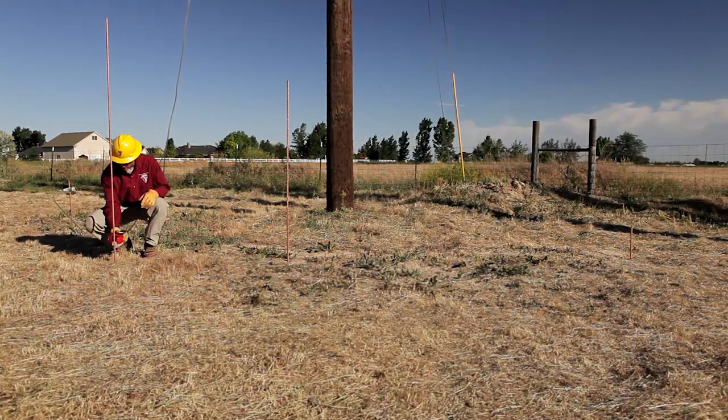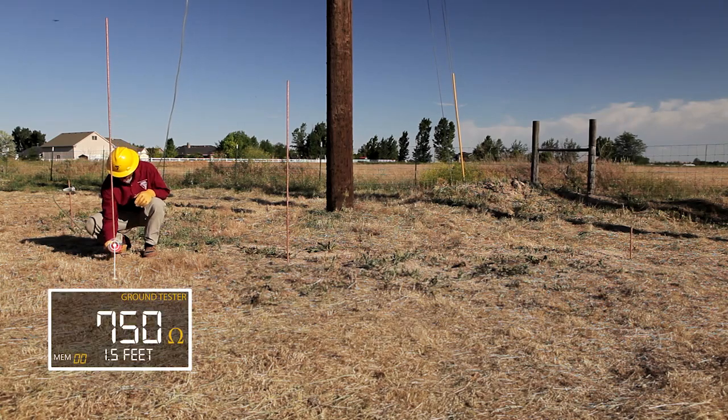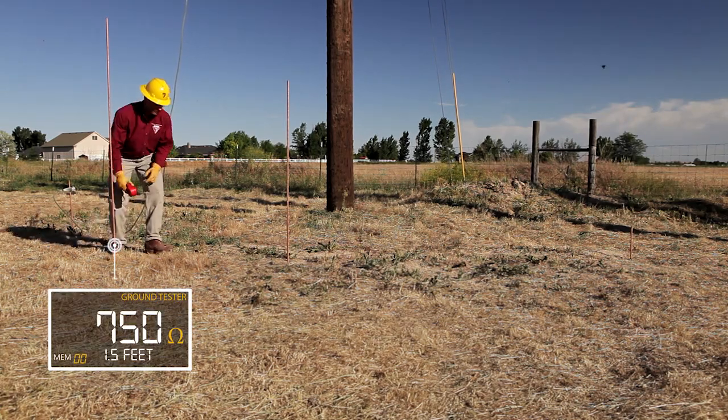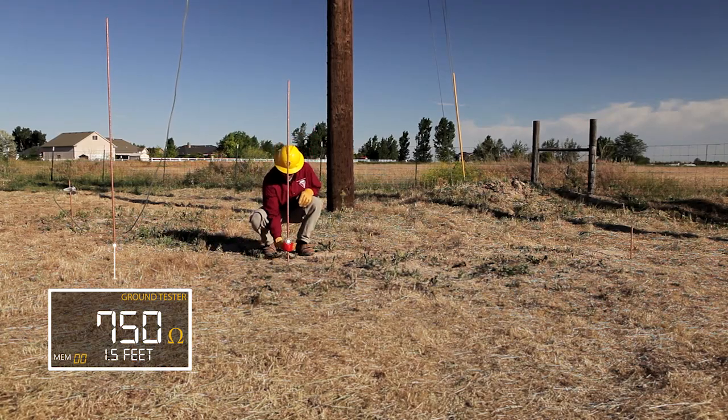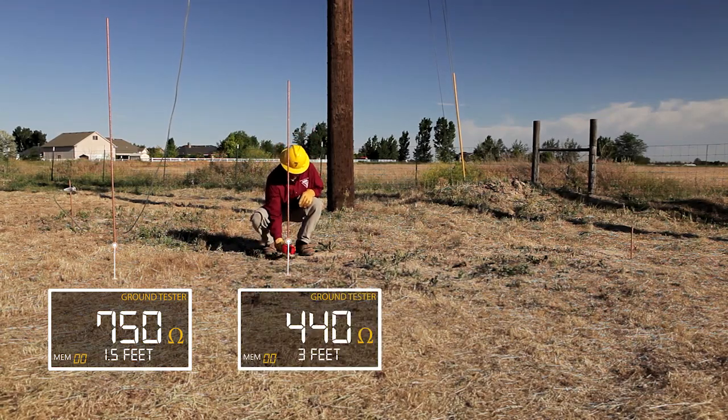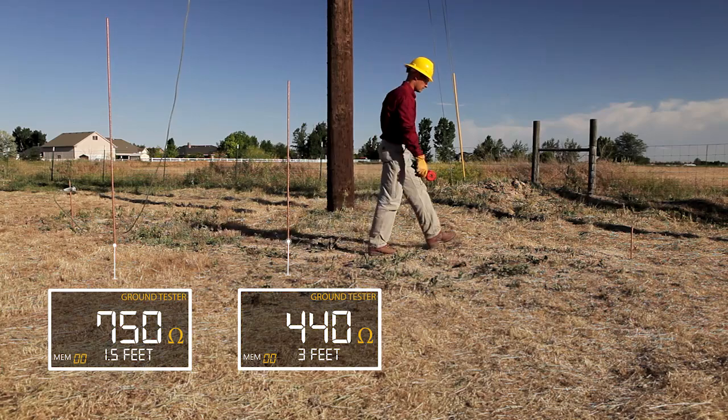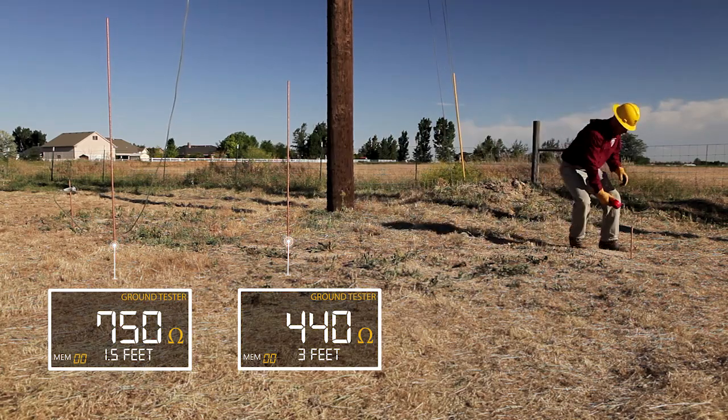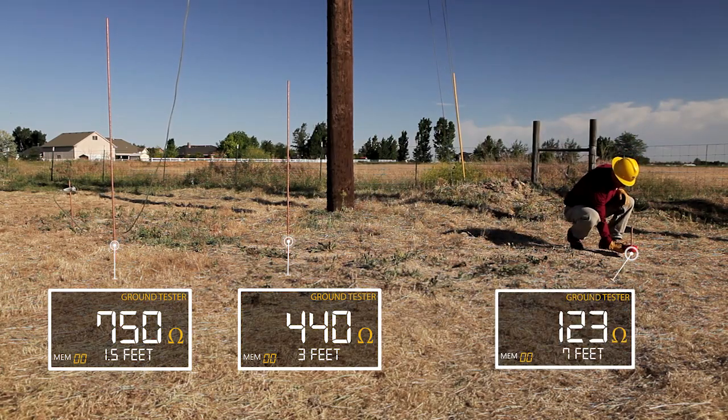Our first ground rod is only driven one and a half feet deep and has a ground resistance of 750 ohms. Our second ground rod is three feet deep and has a ground resistance of 440 ohms. And our last ground rod was driven seven feet deep and is reading 123 ohms.